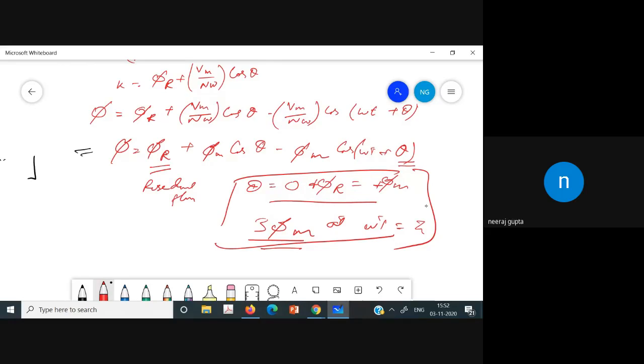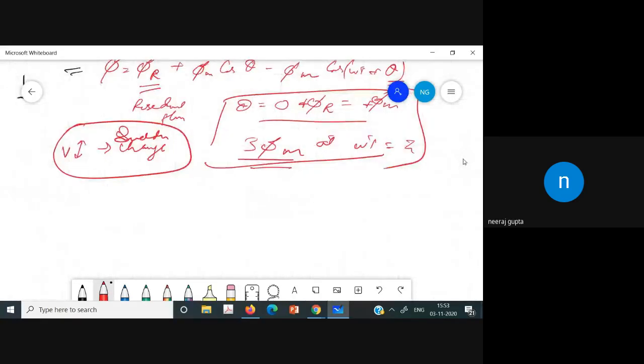However, inrush is also experienced whenever there is a sudden change in the system voltage, such as a sudden recovery of the system voltage when we are clearing a fault. Also, when an unloaded transformer is being switched on, another transformer in the vicinity also experiences a small degree of inrush, which is known as the sympathetic inrush.